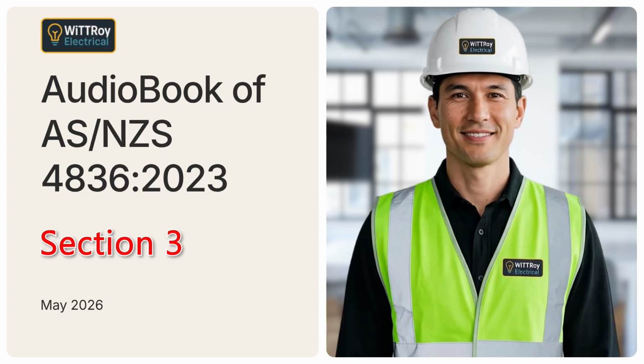That brings us to the end of Section 3 of AS/NZS 4836. This section gives the practical safety process for isolation, proving de-energization, locking and tagging, temporary bonding, identifying the safe work area, fault finding, and testing.